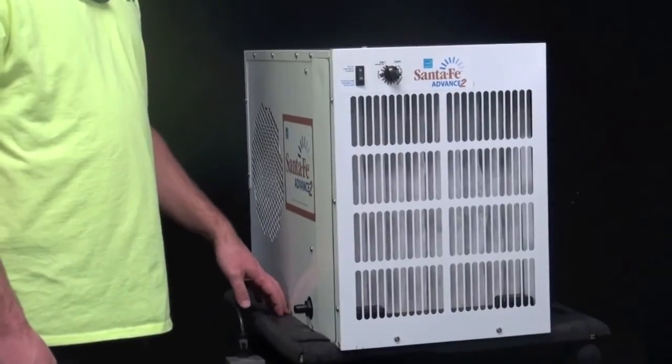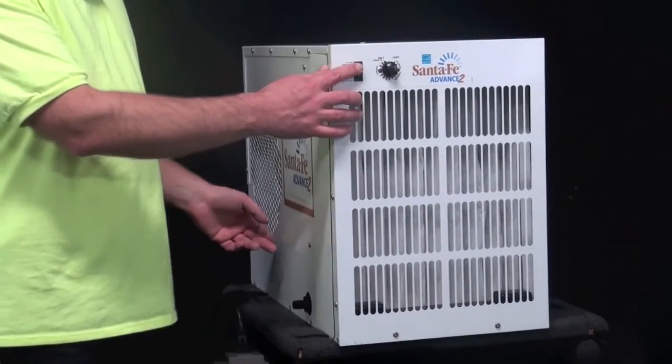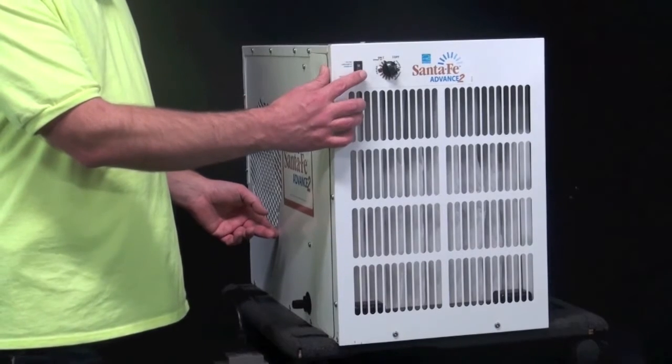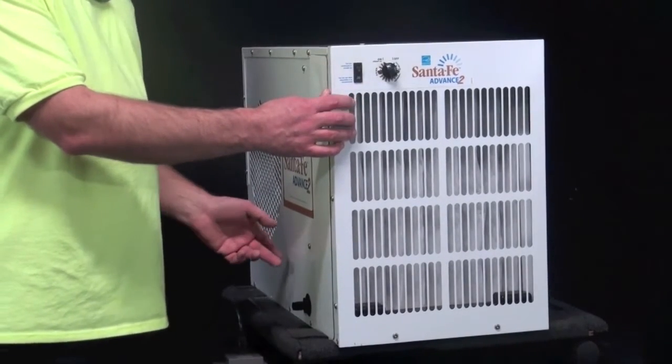Once you confirm that the fan and the compressor are running, go ahead and flip the fan switch from fan on to fan auto. From here, you can do what we call a performance test.